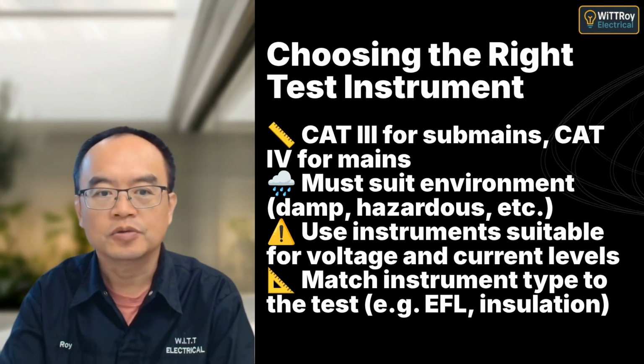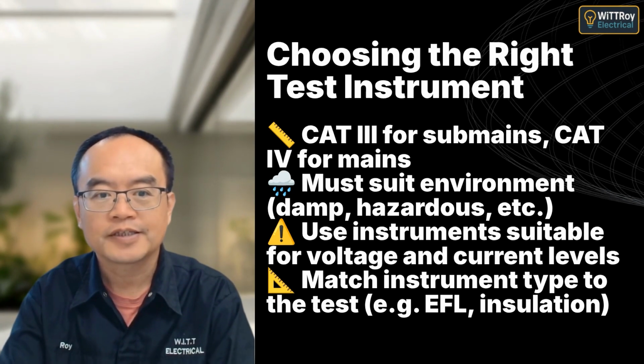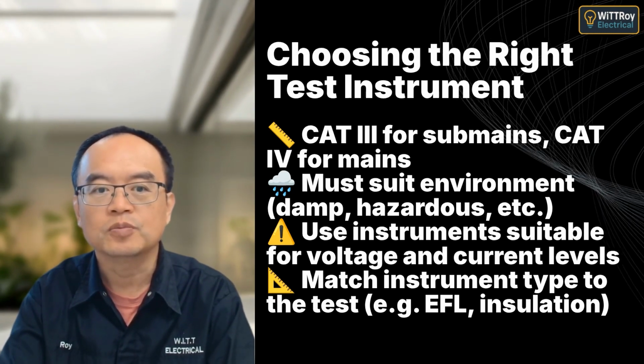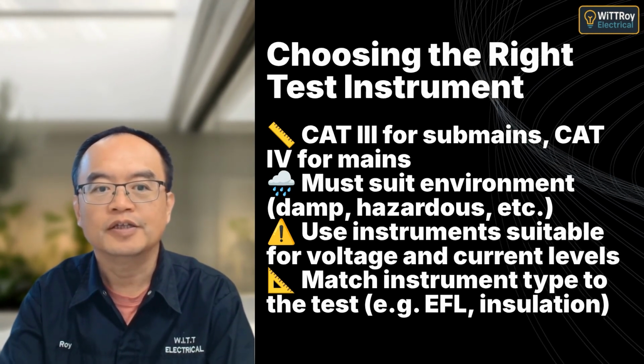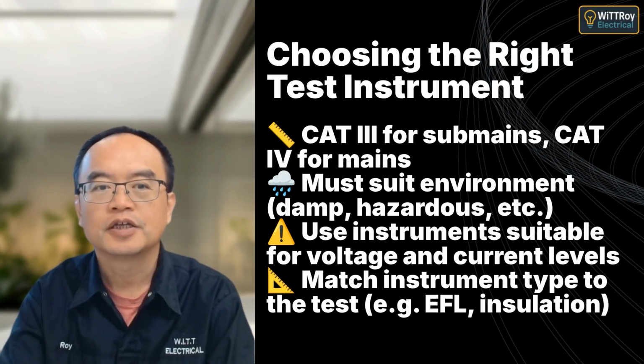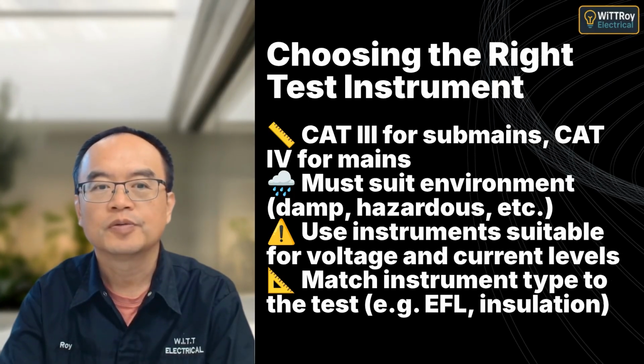Use Cat 3 instruments for submains and Cat 4 for mains testing. Your test gear must be suitable for the site environment, especially in damp or hazardous areas. The instrument's function, range, and safety rating must match the job.